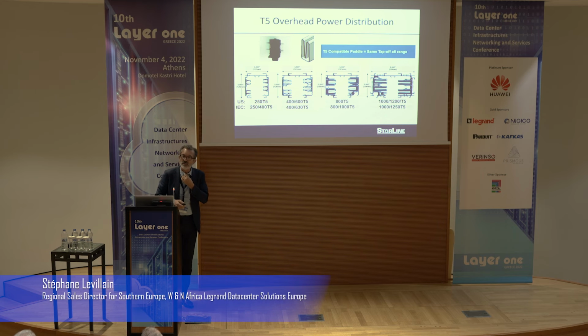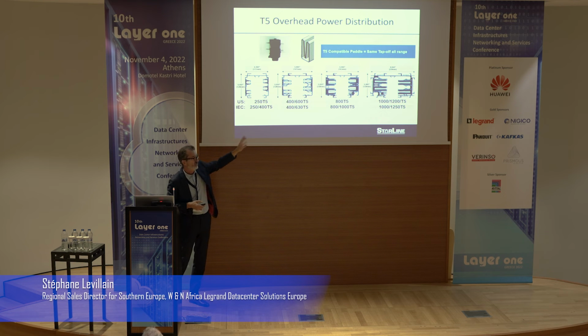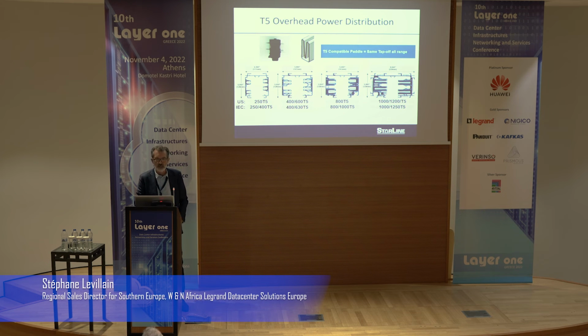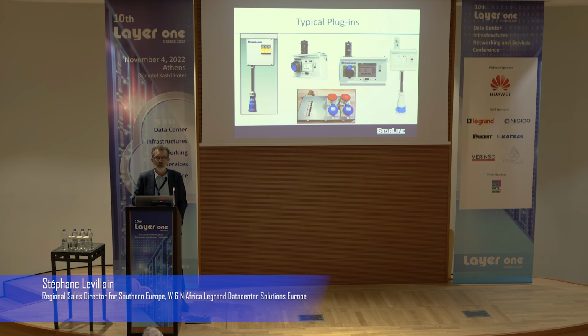When it comes to the Starline range, we start at 250 amp and we can go to 1250 amp. It's the same paddle. The paddle, the black piece there, is the same. You can use it in the 250, in the 630, 800, 1000 amp. It's the same head. So compatibility is 100%. We will get in 2023 a 500 amps range to make the link between the 400 and 630, and that will be available in mid-2023. As I told before, many types of typical plug-ins with metering, no metering, drop cords, receptacle, fuses, MCBs. We can do what you want according to the design. We just need to discuss together to find the best and most efficient solution.